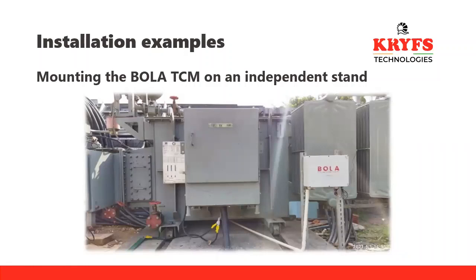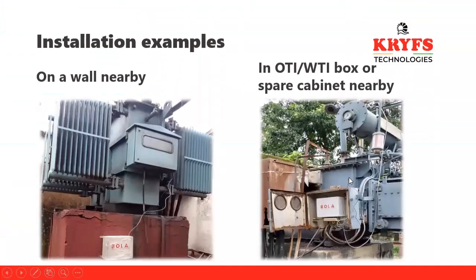Here you can see a large transformer with a substation, and we have installed the BOLA TCM on an independent stand near the transformer. The wiring is done through a PVC conduit. Secondly, this is the majority of applications: we find a wall nearby the transformer, install the BOLA TCM there, and connect the wires to the sensors. If we have a nearby cabinet, or need to install the system in the control room, that is also possible, and can be done in this way.